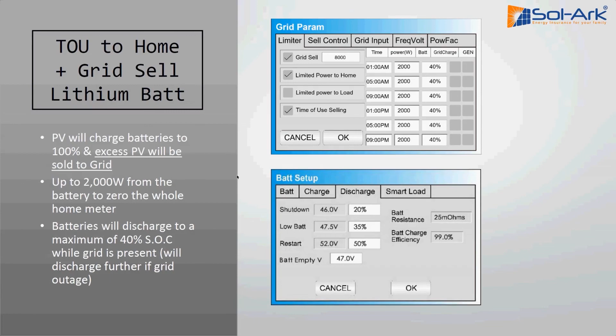So you're in grid sell, limited to home, and time of use. So during the day, you'll sell excess PV power to the grid, and then at night, you'll only sell to offset the house's power usage from the batteries, and so on. And a quick note here is that these percentages on the right are just the minimum allowable SOCs. If you have solar power, the system's always going to try and keep the battery as full as possible, given the situation. But if you're not using that much power in the house, or you have enough solar to offset the whole home usage, it will charge up the battery bank as well. And then over here, 2,000 watts from the battery, 0 to the home meter, and batteries will discharge to a maximum of 40%. Okay, yep.